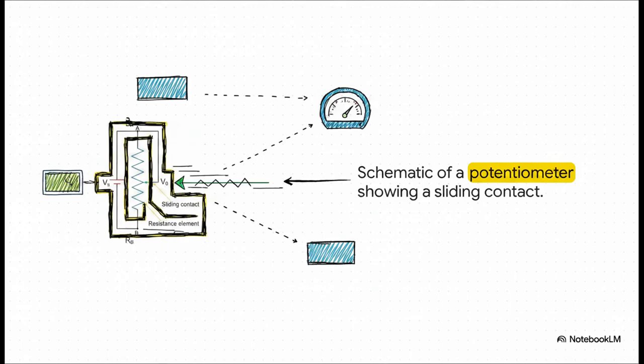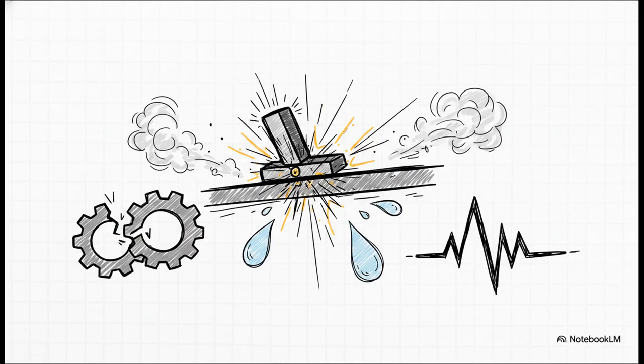Pretty clever, right? But while they're simple and cost-effective, potentiometers have some tangible physical drawbacks. Because they rely on parts literally dragging against each other, they require a relatively large force just to move the wipers. And worse, those sliding contacts are fully exposed to the environment. They can get contaminated by dust, oil, moisture, you name it. They are prone to actual mechanical wear and tear over time, and can get misaligned from vibration. As they physically wear down, they generate frustrating electrical noise that disrupts the signal.